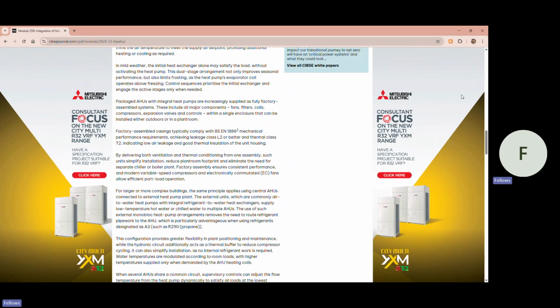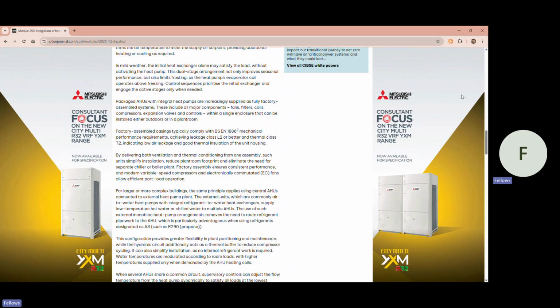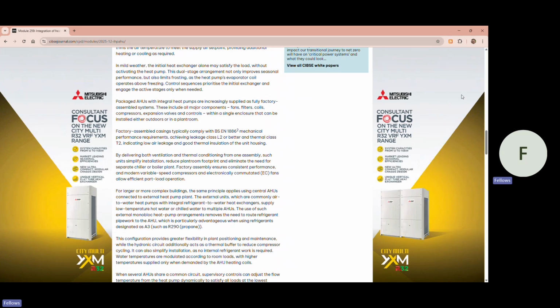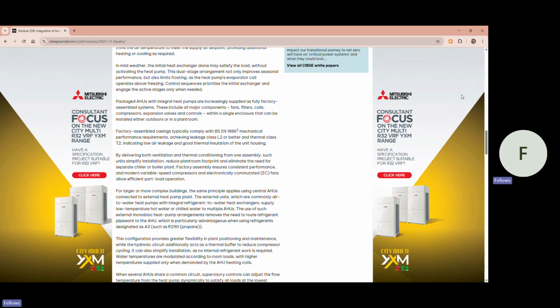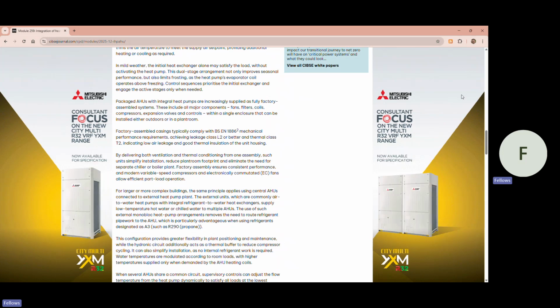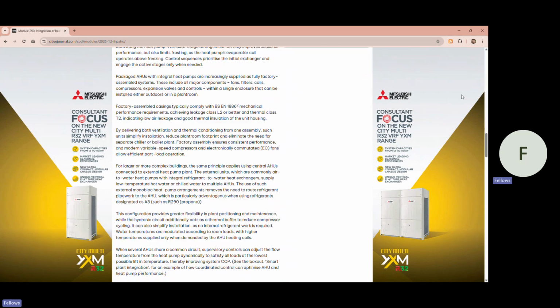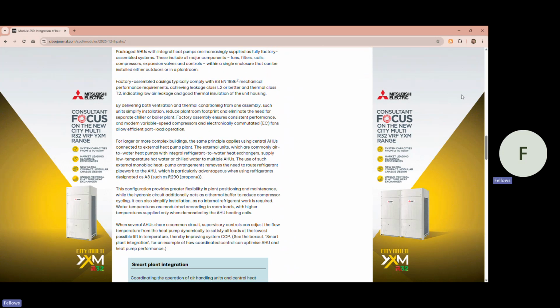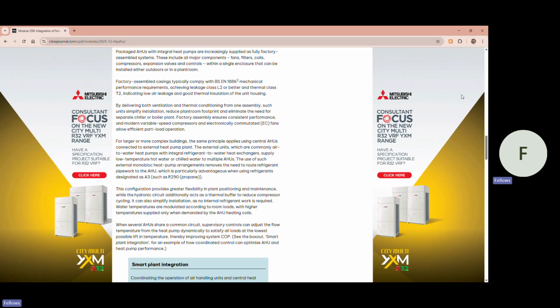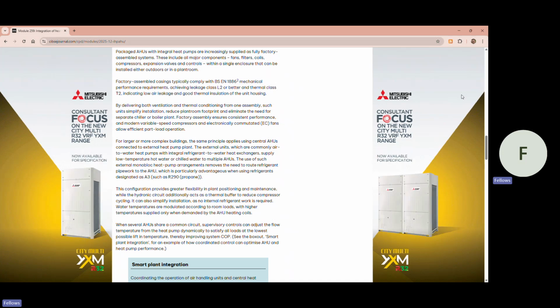By delivering both ventilation and thermal conditioning from one assembly, such units simplify installation, reduce plant room footprint, and eliminate the need for separate chiller or boiler plant. Factory assembly ensures consistent performance with modern variable speed compressors, and electronically commutated or EC fans allow efficient part load operation. For larger, more complex buildings, the same principle applies using central AHUs connected to external heat pump plant.